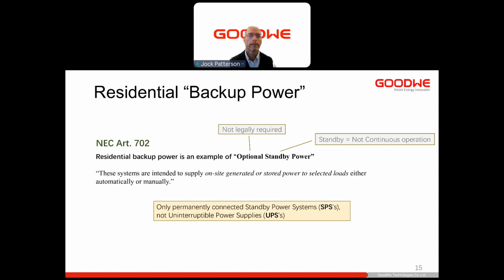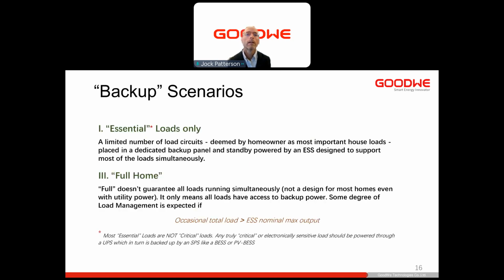Distinction that's important is these systems are standby power systems, not uninterruptible power supplies, meaning that we can't guarantee there isn't a significant latency to the transfer time from a loss of grid to the backup system. We'll be talking more about that. So we have essential loads, which are those few circuits that the homeowner would really like to be backed up. And that's a simpler solution generally, right? Sometimes it can be difficult to do essential load wiring, but generally it's a simpler solution.